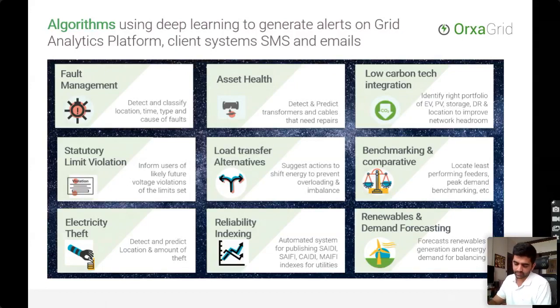If you have a large asset base of more than say 100 or 1,000, or 10,000 cable sections, you cannot test all of them every day. So the asset health algorithm classifies your asset base into health index bands, between health index 1 to 5. These bands tell you which assets are in healthy, good working condition, and which are in a risky or about-to-fail condition, so you can prioritize and optimize maintenance strategies to focus on assets that require further attention.